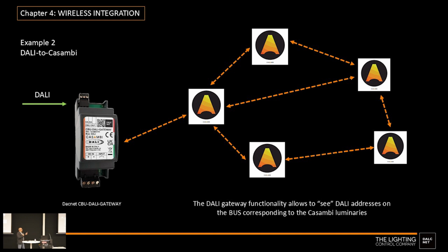The device works extremely well, because when I insert the DALI gateway into the Casambi network, I can scan the DALI bus connected on the gateway, and it shows me how many DALI addresses as Casambi luminaires I have. So every Casambi luminaire in the Bluetooth mesh network corresponds to a DALI address—for example, RGB luminaires are DT8 addresses. There's also the possibility to export sensors and switches, so the integration is very smooth and works very well.